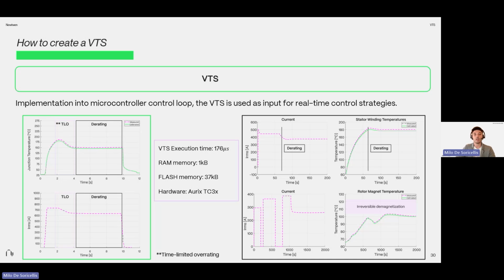We can design and place the virtual thermal sensor at the hotspot, or leverage multiple virtual thermal sensors, and use this information in the control loop to derate the power according to the real-time estimated temperature of the winding.